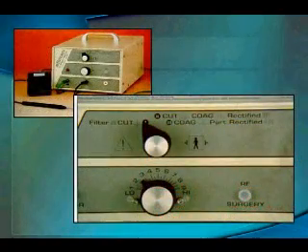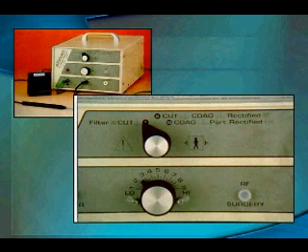All radiosurgery units comprise a transformer to change the main voltage to a high voltage and high frequency current. This high frequency current is then further modified by filtering and rectification to produce one of 4 radiosurgical waveforms: filter cut, cut and coag, coag or hemo, and fulguration.